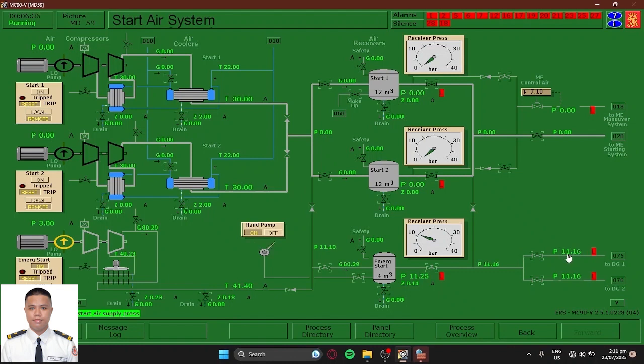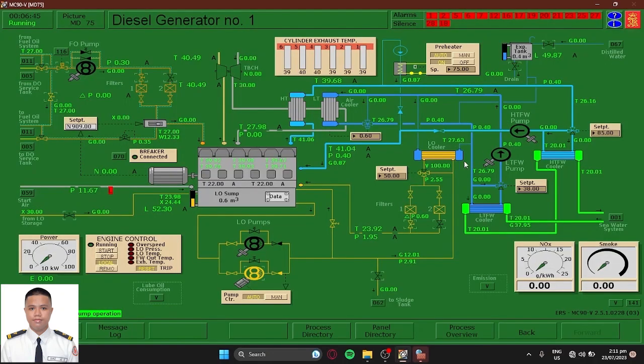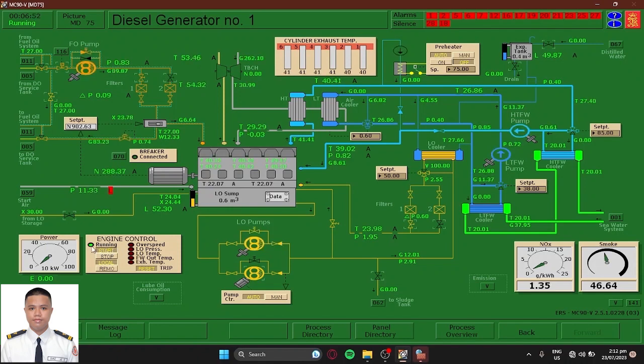So I've already achieved 11 bars. We can cut this valve off, turn this valve off, and turn the hand pump off. So let's go back to diesel generator 1. Let's start the diesel generator 1 here. We're pressing this start. So the engine is now up and running. Let's set this to remote.